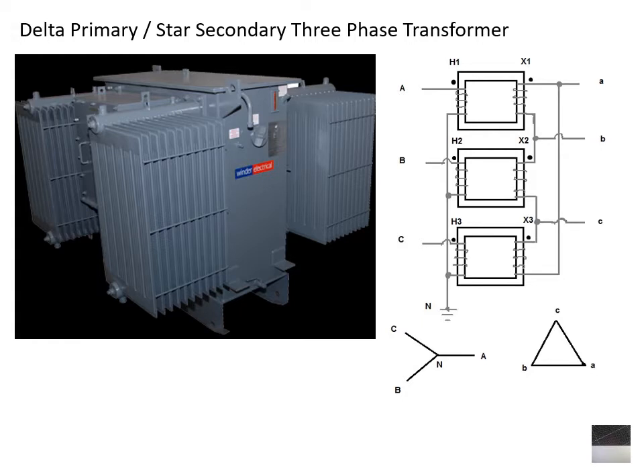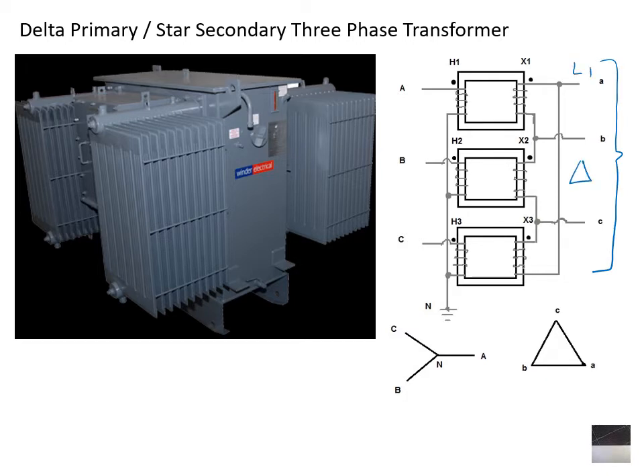A typical transformer is air-cooled with radiators, often oil-filled — you can see the drain at the bottom for servicing. Some are oil-filled, some air-cooled, some force air-cooled with fans, depending on size and load. Looking at the transformer diagram, on the primary side this is a delta connection, with three phases L1, L2, L3 — this could be 11 kilovolts on the high voltage side.